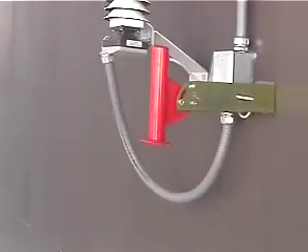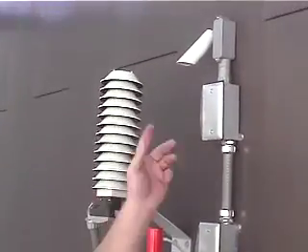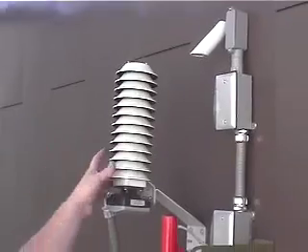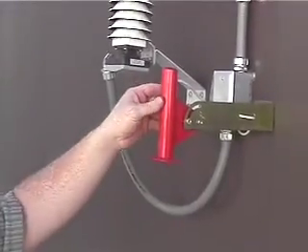Okay, so now we're over on the east side of the roof, and here I'm going to show you your outside air temperature sensor, outside air humidity sensor, and your building pressure sensor for the atrium. The temperature sensors all run down to the air handler that's down here, which is air handler 1. So that's where the physical connection is, and that runs everything here. That particular outside air sensor does the whole building.